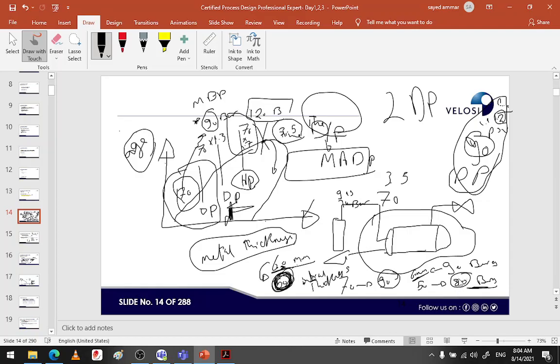Did you get it, Muhammad? Yes, thank you very much, much appreciated. This is called risk-based inspection, done by your asset integrity department. And the thickness, for vessels and any of the equipment, should be the weakest point, Muhammad, not the average. If this separator has one point here and one point there, and this is 88 and this is 70, we will apply the rating to the weakest point, the lowest, just to avoid the rupture. Okay, thank you very much. You're welcome.